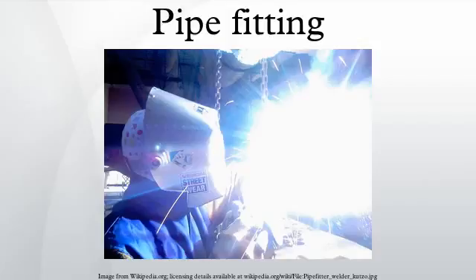If heated and allowed to slowly cool, called annealing, then rigid copper will become soft and can be bent and formed without cracking. Soldered connections. Solder fittings are smooth, and easily slip onto the end of a tubing section. The joint is then heated using a torch, and solder is melted into the connection. When the solder cools, it forms a very strong bond which can last for decades.